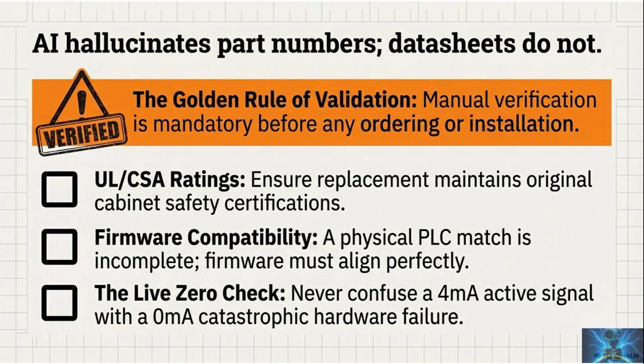AI hallucinates part numbers. Datasheets do not. This is the reality check slide. AI can invent part numbers confidently. Datasheets and manuals do not. The golden rule of validation is simple. Manual verification is mandatory before ordering or installation. Check UL and CSA ratings, so the replacement maintains cabinet safety certifications. Check firmware compatibility, because a physical PLC match is not the whole story. Check the live 0 rule, so you never confuse 4 milliamps active signal with 0 milliamps catastrophic failure.